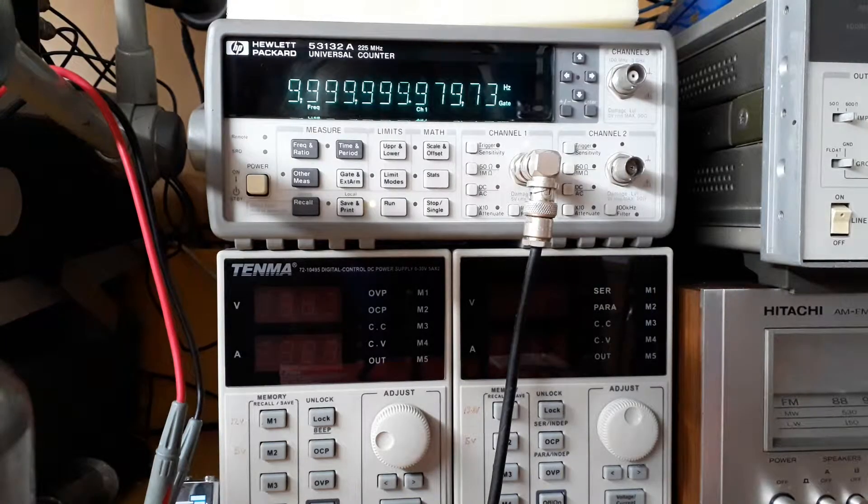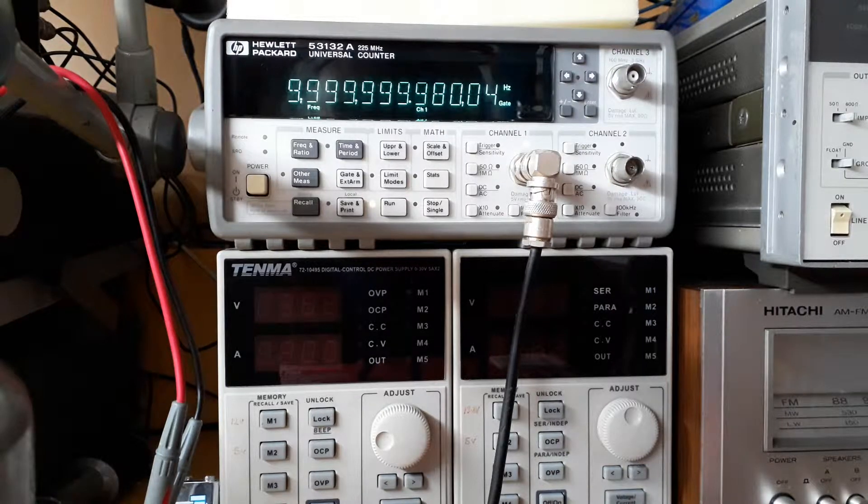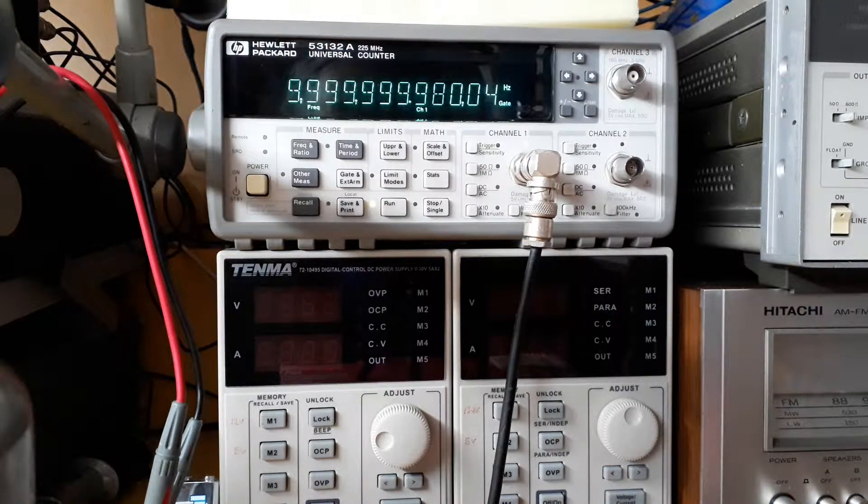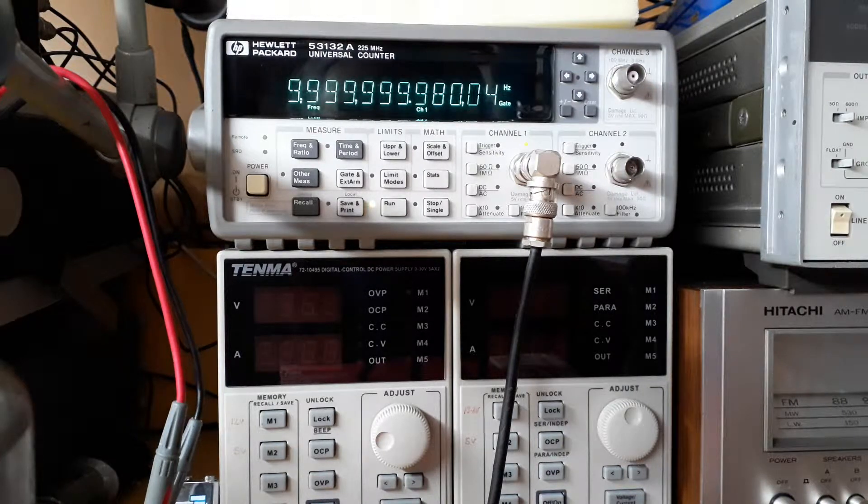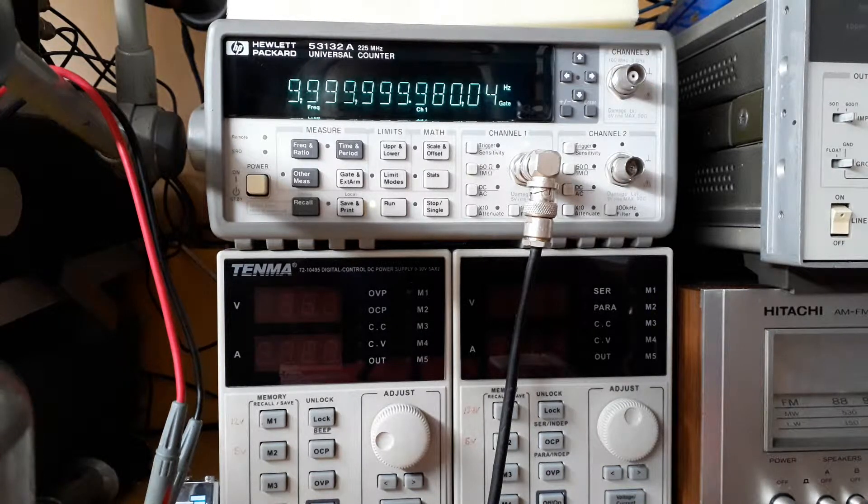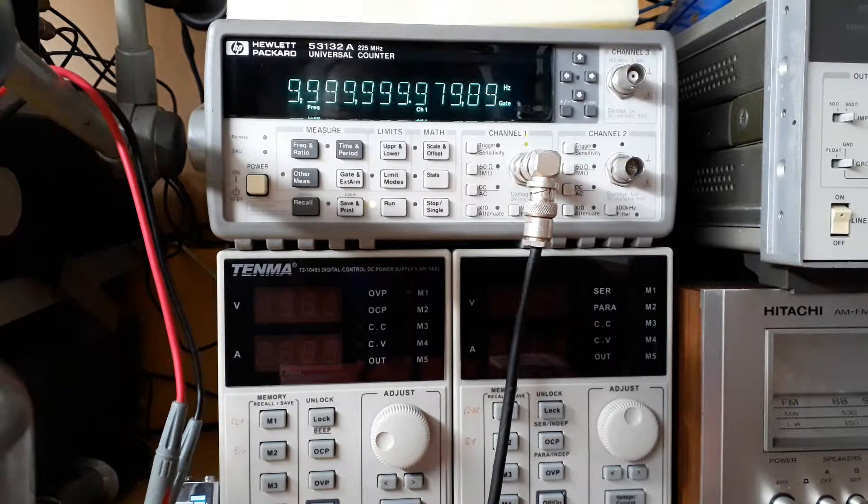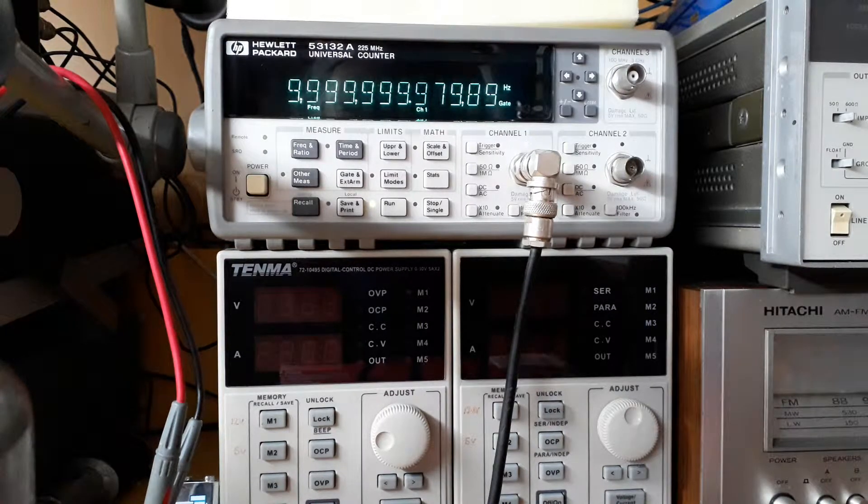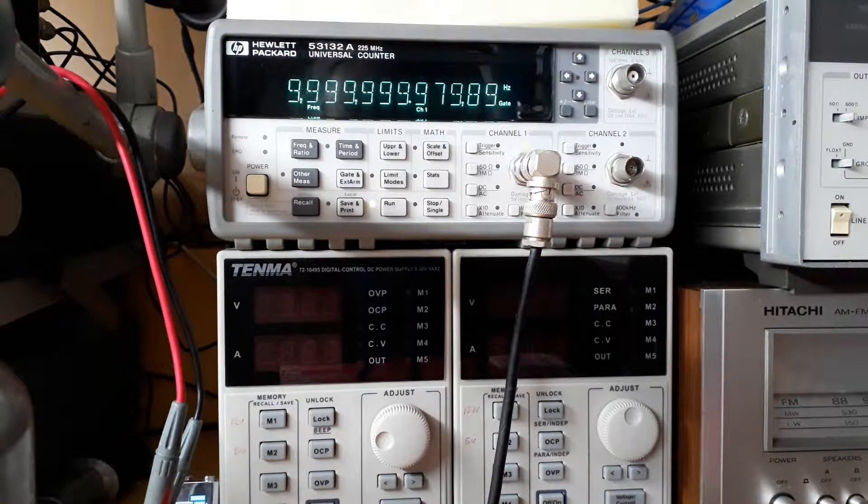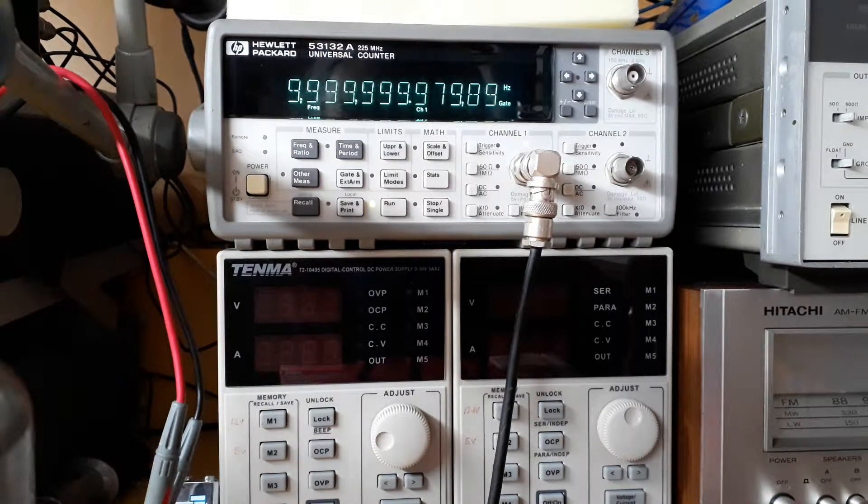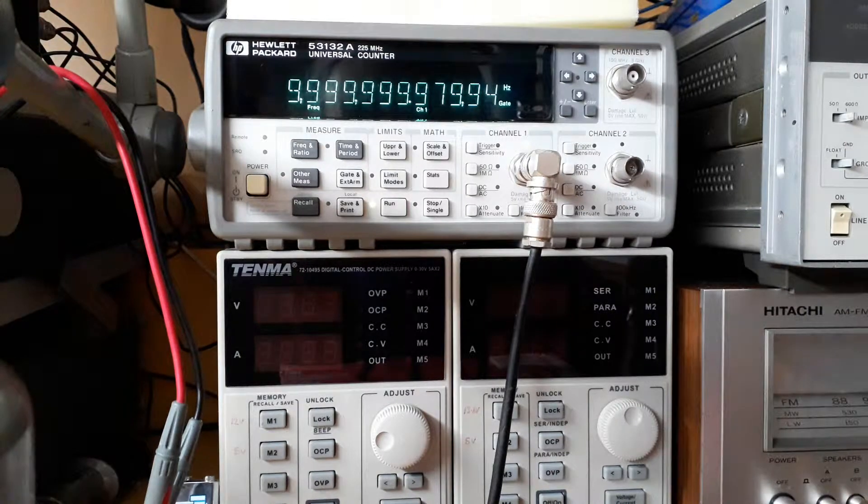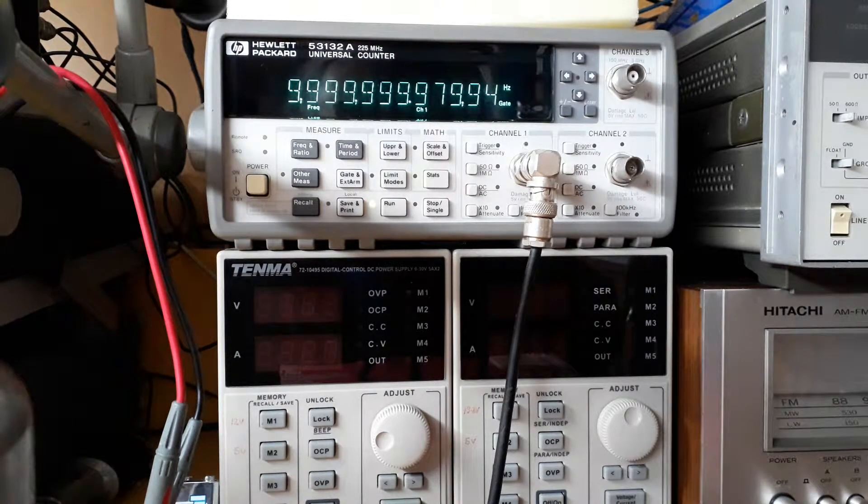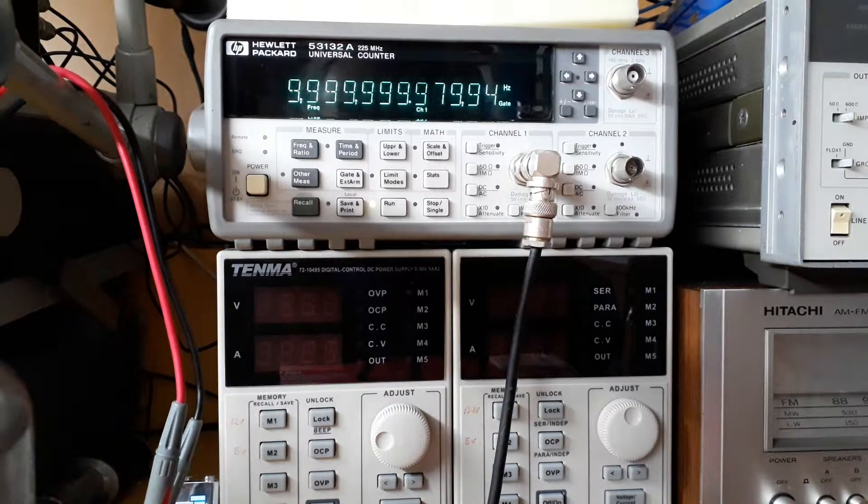So here we are, roughly two days after I last did the time-based calibration on the new OCXO. And when I did the calibration, it was reading approximately one millihertz high. You never get perfect accuracy after a calibration. In theory it should be all zeros. But I think that's down to the DAC they're using. It's a 12-bit DAC.